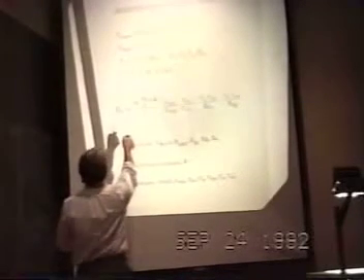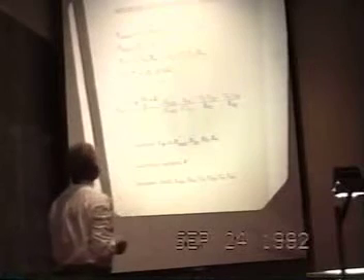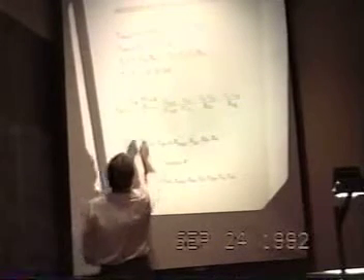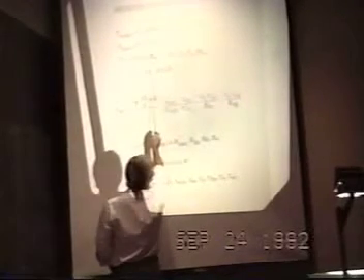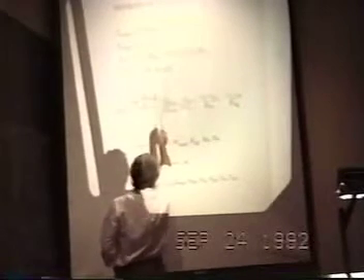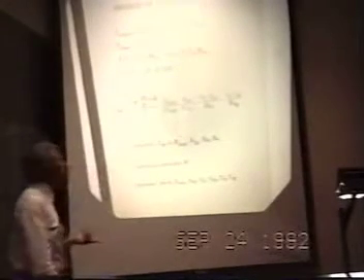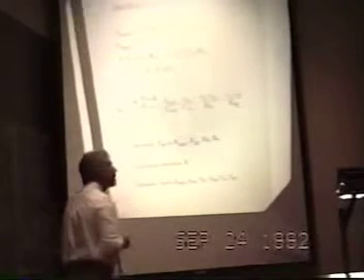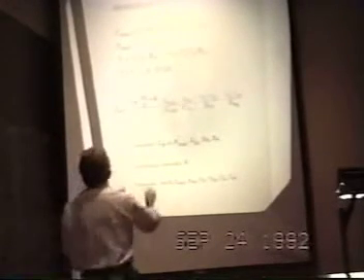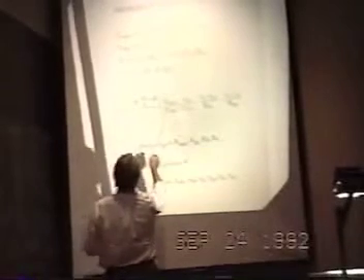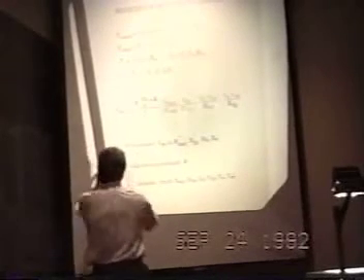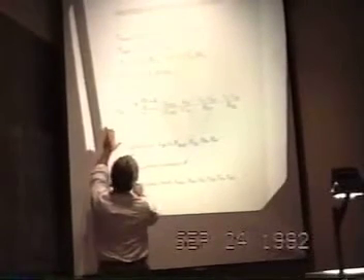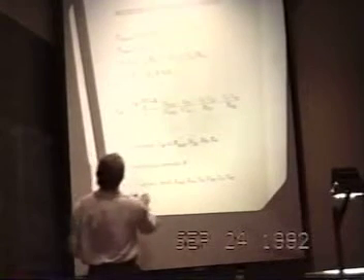Temperatures are measured with platinum resistance temperature devices, so they are measured in terms of the resistance of the RTD element, normally something like 100 ohms, where the coefficient alpha is the known slope of the temperature resistance coefficient of platinum.